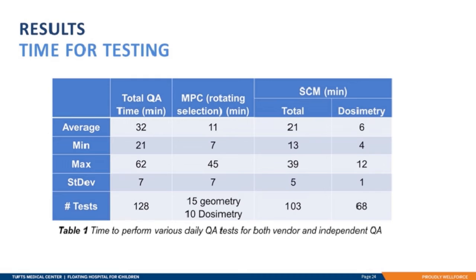Machine Performance Check took approximately half the amount of time as a full daily QA using SunCHECK Machine, but performed significantly fewer tests. Overall, half an hour for daily QA, especially for the number of checks performed, is very reasonable. It is on par with the time that had been spent on daily QA on our previous system. That system, however, did not meet the recommendations of TG-142, and fewer tests were performed. So overall, there was a noticeable improvement in efficiency with our new system. Our radiation therapists also noticed this and appreciated it.